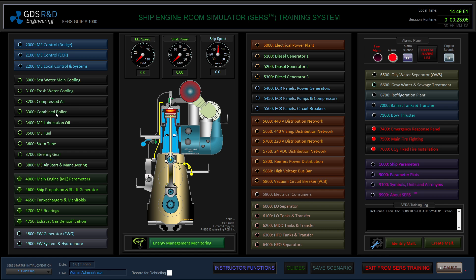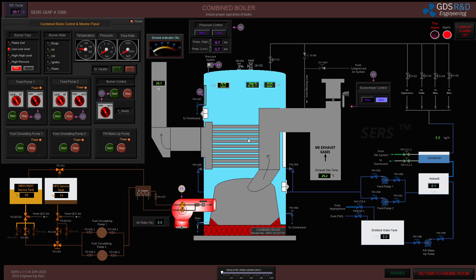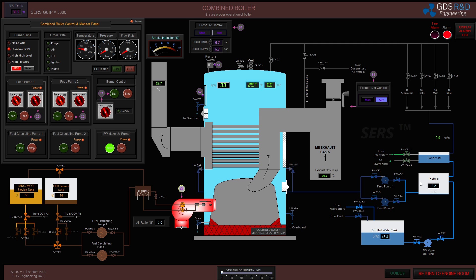By the time the air compressors run I will start my boiler operations. As you can see, the distilled water tank is empty right now. I will fill the tank from hydrophore, and with that distilled water I will fill up the hot well using the fresh water makeup pump. Then this water will be used inside the boiler to build up steam pressure, start steam circulation, and through the condenser it will return back to the hot well.